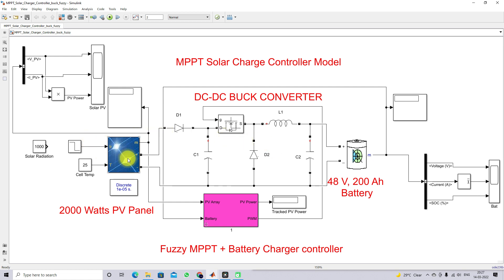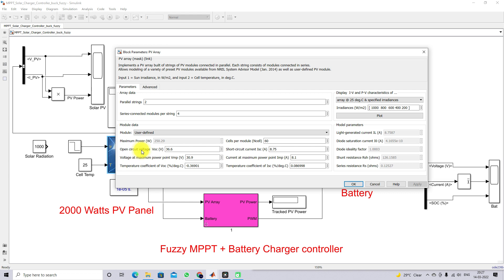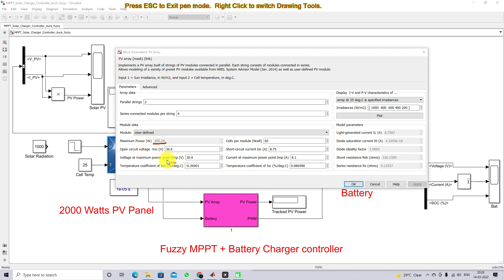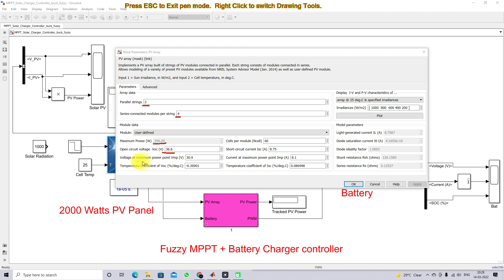This model consists of a 2000-watt PV panel. The single panel rating is 250 watts. We are connecting four panels in series and two parallel strings, so connecting four panels in series gives 1000 watts, and with two parallel strings the total power is 2000 watts. The single panel open circuit voltage is 36.6 V, the voltage at maximum power point is 30.9 V, the short circuit current is 8.75 A, and the current at maximum power point is 8.1 A.